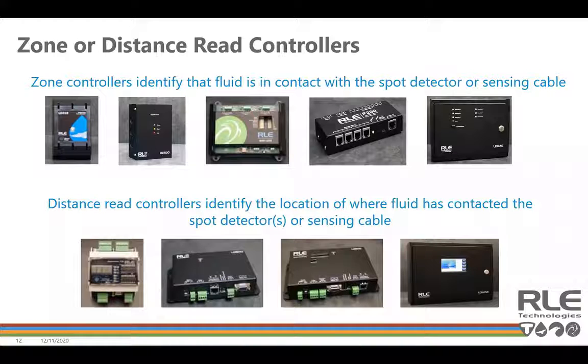So the distance read controllers that you see at the bottom are ideal for protecting larger spaces. They'll specifically pinpoint where along the length of the sensing cable, or at which spot detector, the leak has occurred. So again, very detailed information, very helpful in getting to the leak quickly, especially in large facilities. So those are the different types of controllers we offer.